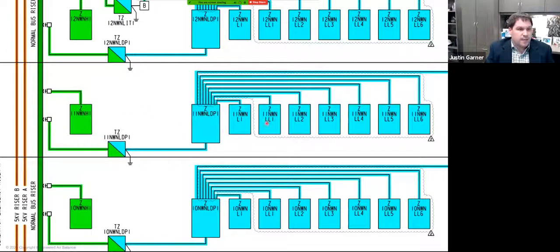So in the case of this view right here, this I think served the office area of this particular facility. And then we had lab wings as well. So obviously this is only being served by normal power. So it's not as critical as, say, maybe the lab areas. More than likely these panels were serving fan powered terminal units and other 480/277 loads. And then you'll see here that we have a transformer that takes everything down to 208/120. We have a distribution panel here that's feeding out to panel boards.